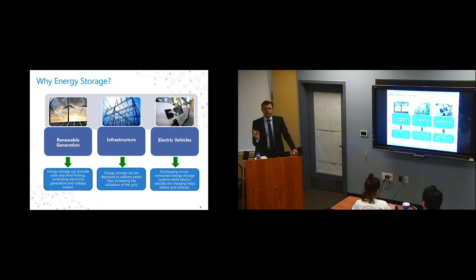There's a component in that tariff called the demand charge. If two commercial neighbors consume the same amount of electrons, the same kilowatt hours by the end of the month, but one consumed it steadily over 30 days and the other consumed it all in a single 30-minute fast charge once a month, their bills would be significantly different, potentially tens of times higher for the one with the burst usage.